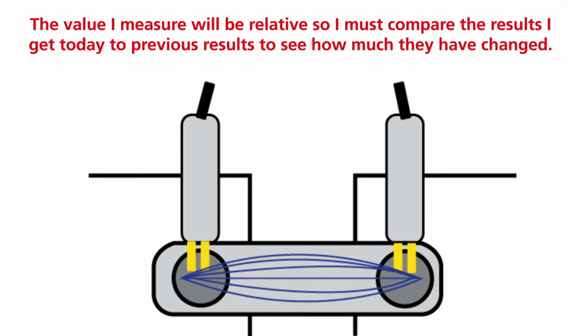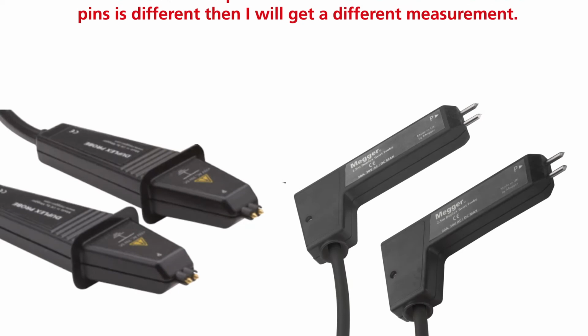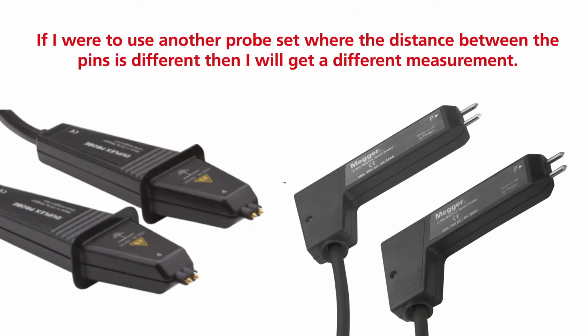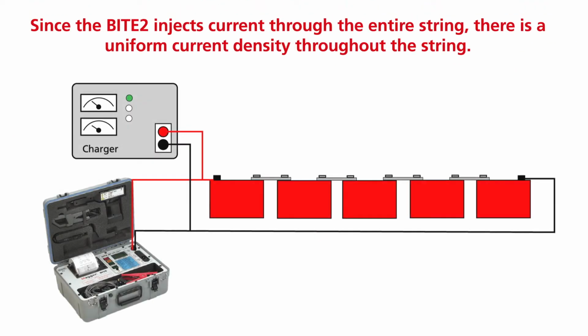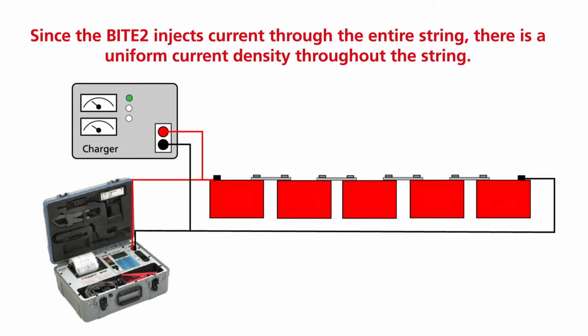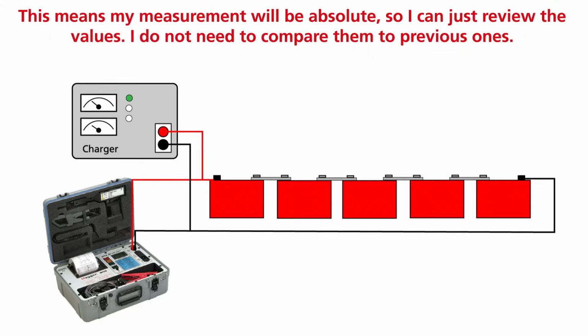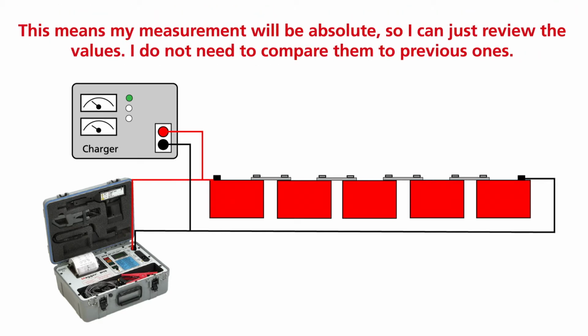The value I measure will be a relative value, so I must compare the results I get today to previous results to see how much they've changed. If I were to use another probe set where the distance between the pins is different, then I will get a different measurement. Since the BITE2 injects current through the entire string, there is uniform current density throughout the string. This means my measurements will be absolute, so I can just review the values. I do not need to compare them to previous ones.